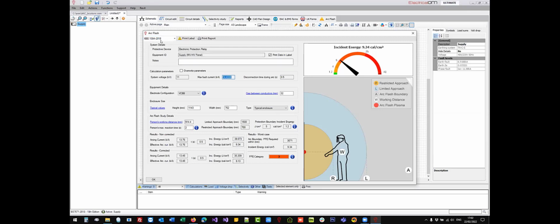Due to the latest standard, we can apply a correction which reduces a little bit the arcing fault level, to see if we can get a slower, let's say, disconnection time, which eventually might lead to a larger incident energy. And the worst case, of course, is the one that we will consider, and in this case it is 9.34 calories per square centimeter, which will give us a category of PPE 3.